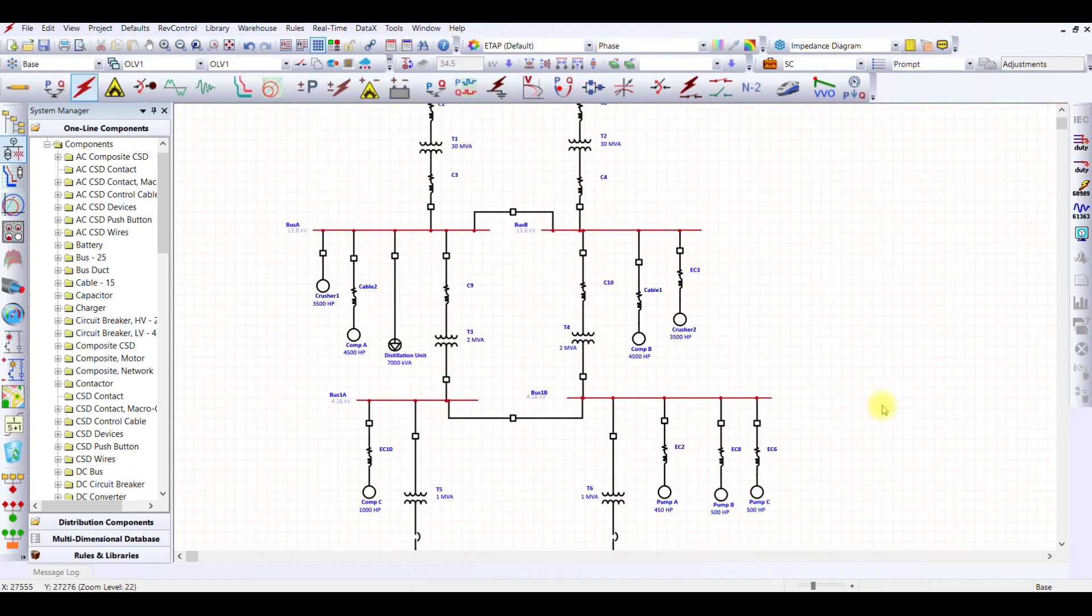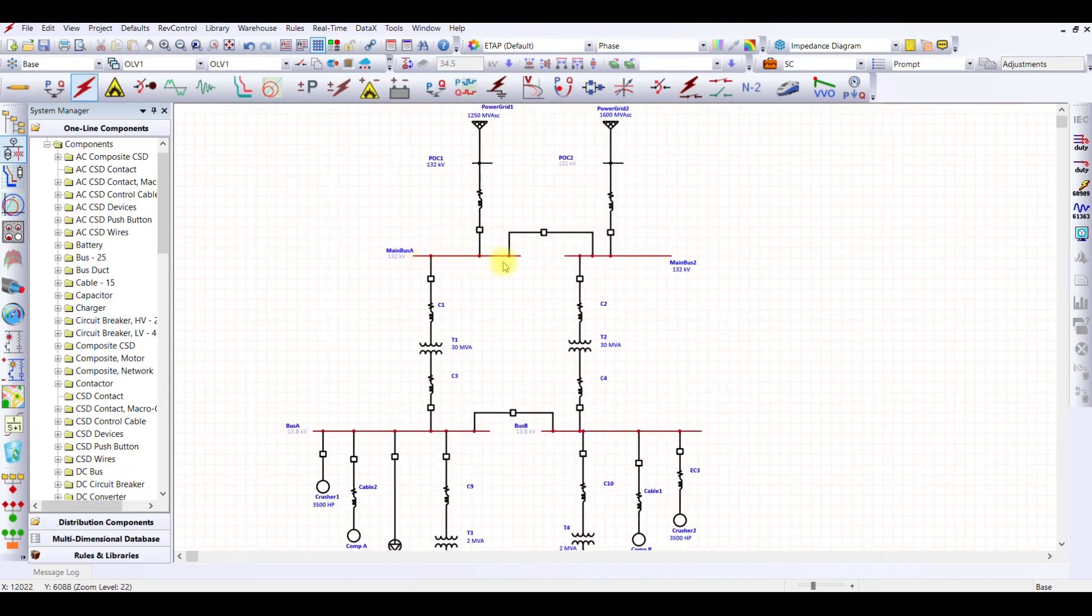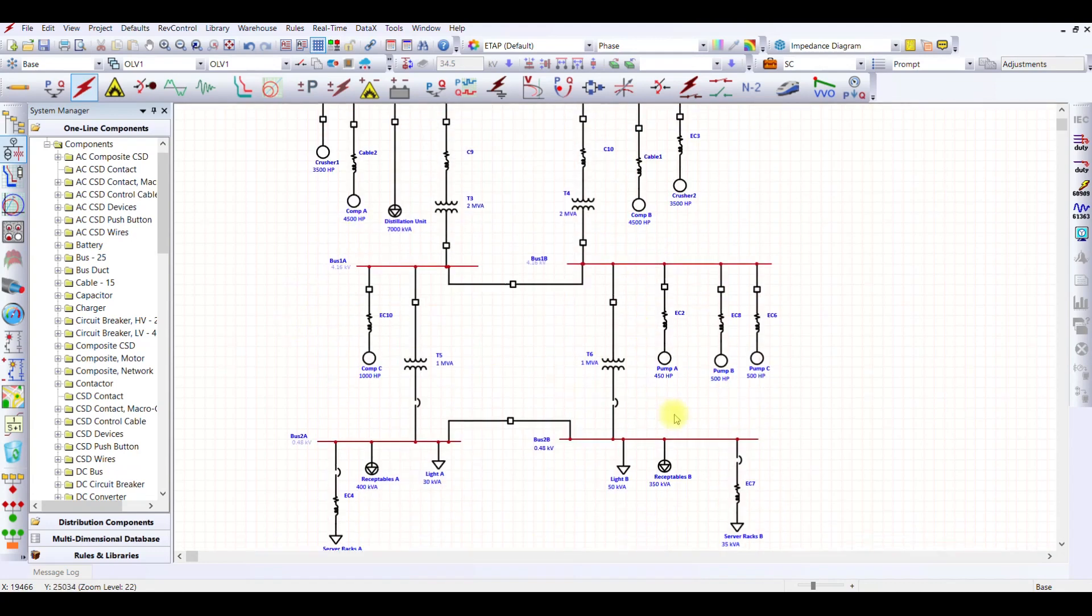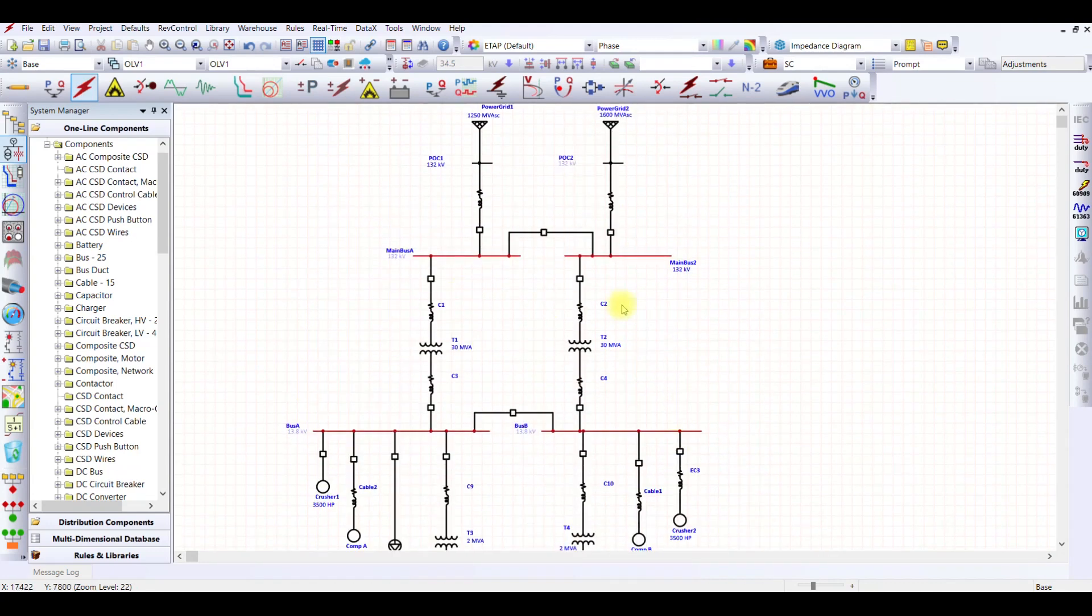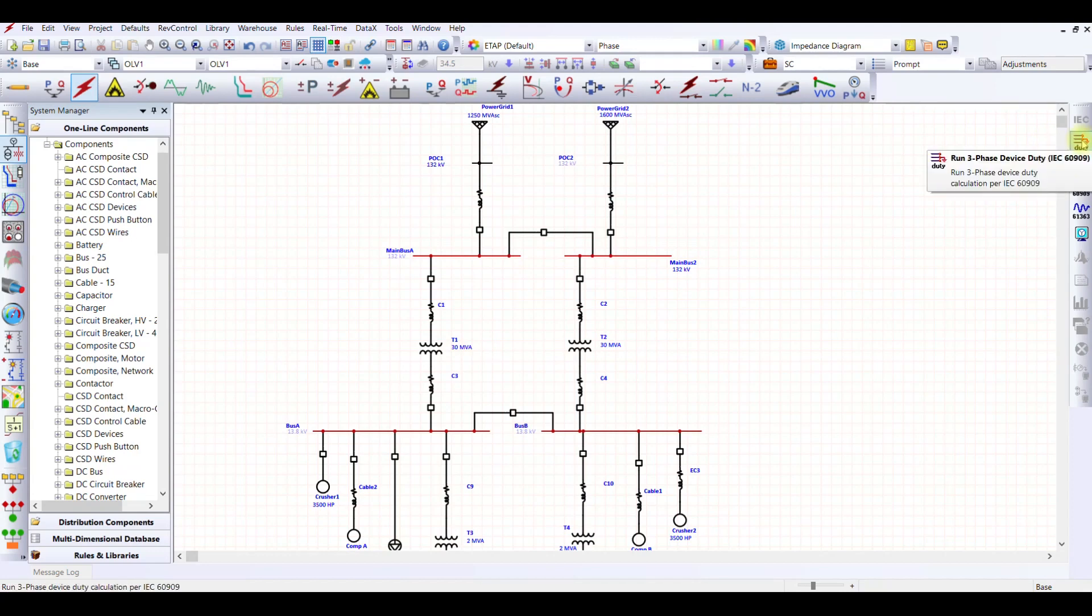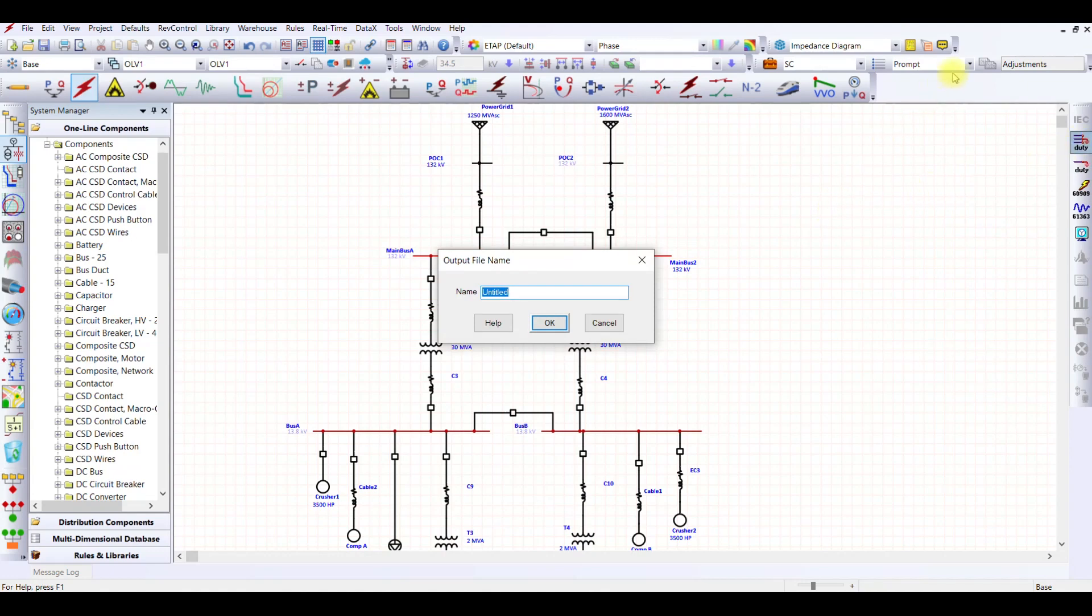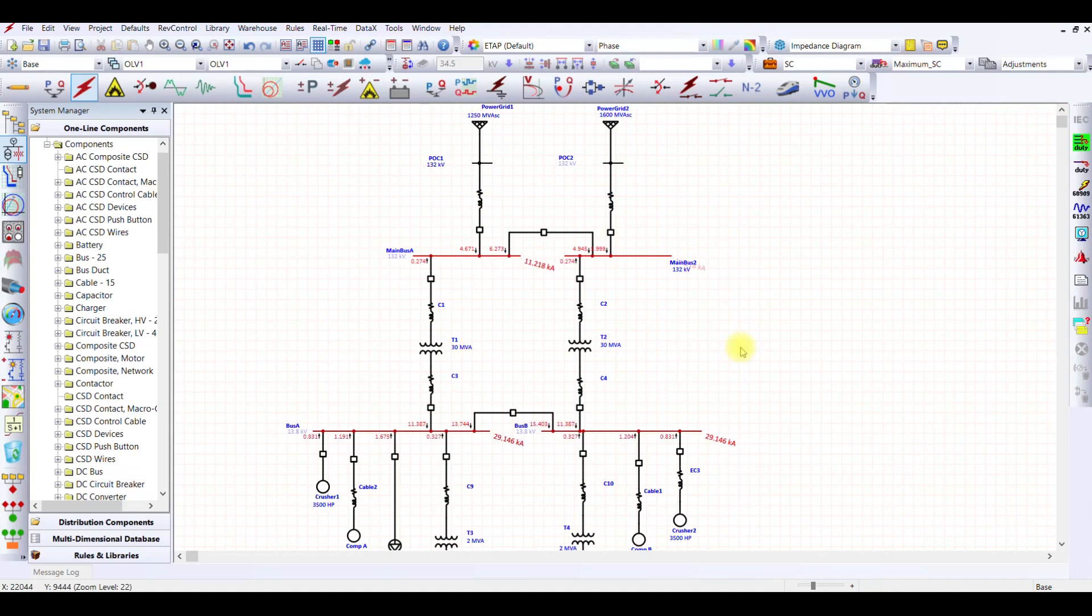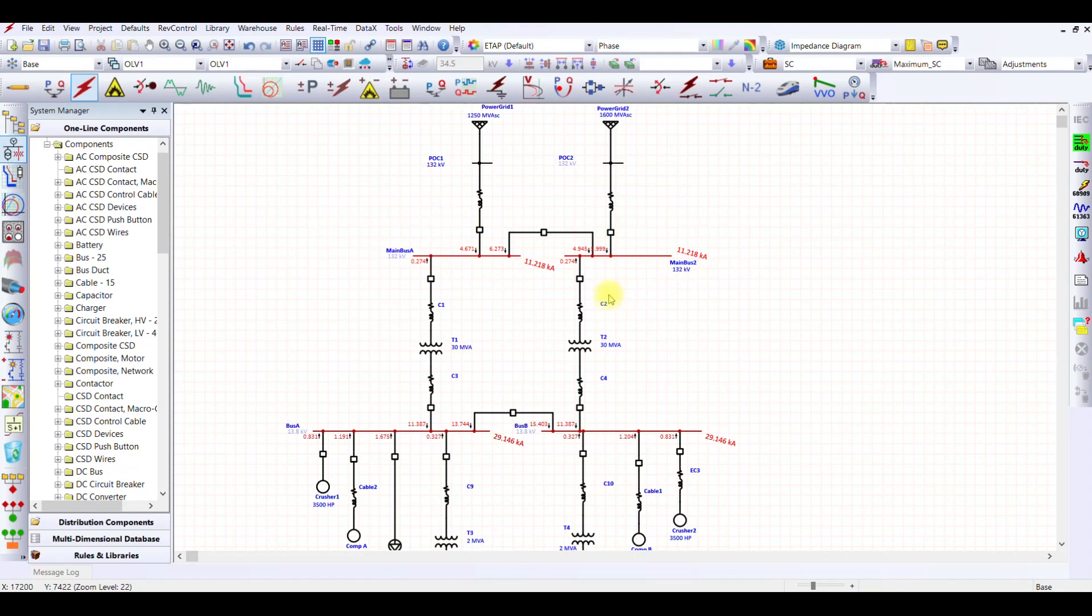Once I am done with this, you see the colors has changed for the buses where I want to perform short circuit analysis. Now what I simply have to do, I simply have to perform this duty. So if I run three-phase device duty, when I click on this, because this was on prompt, it is asking what should be the name of my file. So I am performing maximum short circuit, so let us select the name of the file as maximum short circuit and press OK. Now ETAP is going to calculate my short circuit level.